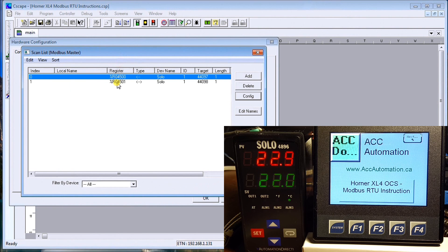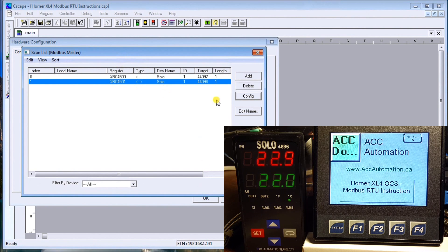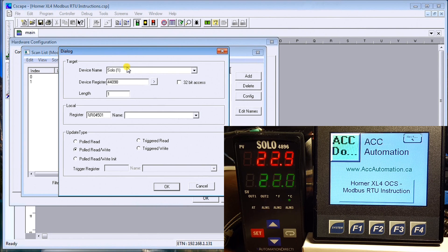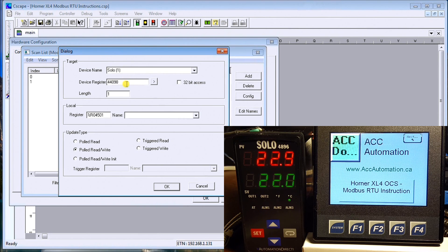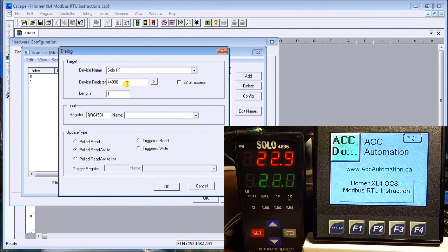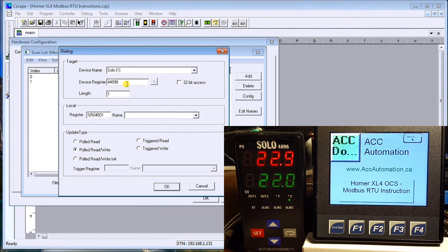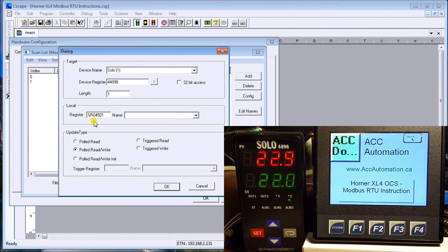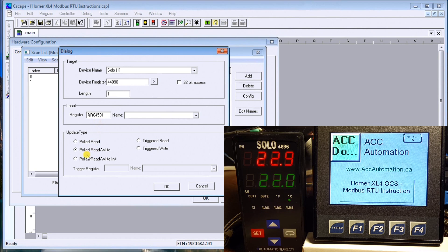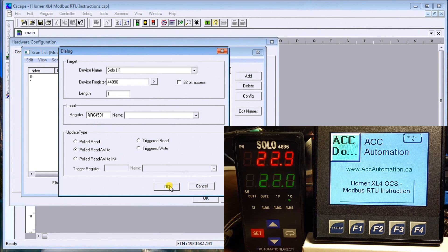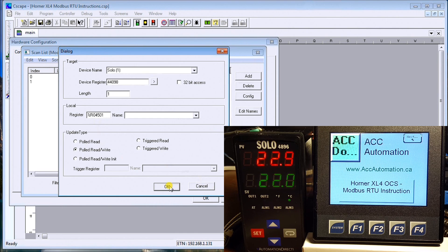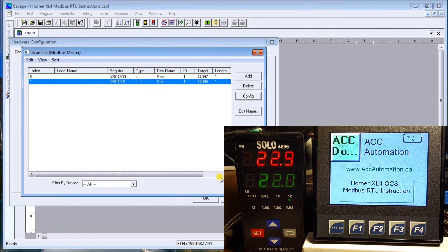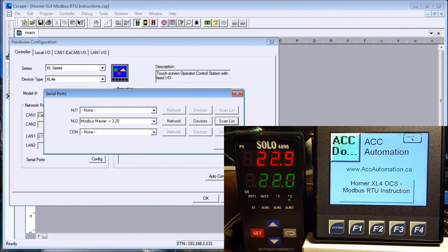The next one, we'll look at the configuration. It's SOLO 1 again, same unit. This time our register address is 44098, which is our read/write. It's one word length as well and goes to register 4501. It's a poll read and write.